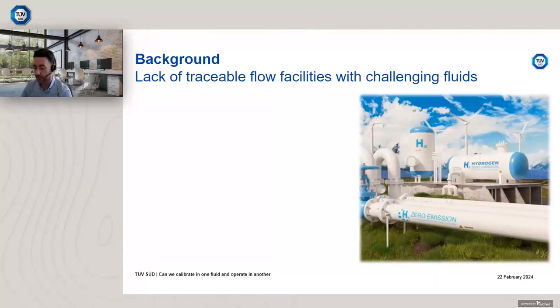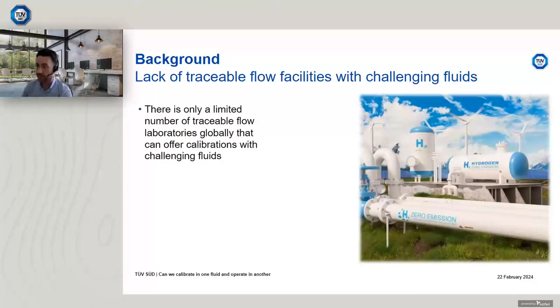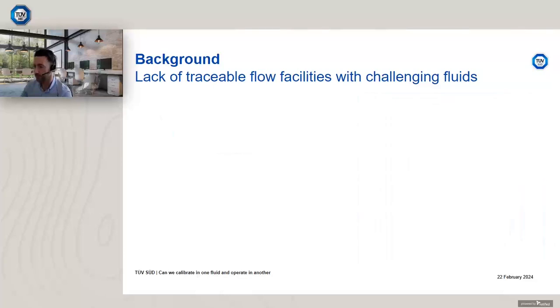Another fluid that is obviously very topical is hydrogen. And again, same as before, there's a limited number of flow facilities. There might be some that can offer gas flow, either in hydrogen flow for gas or liquid, but they're typically very, very small flow rates. There might be applications with hydrogen refueling stations, for example, very low flow, or domestic gas use trials, which we're also completing here at TÜV SÜD for gas phase hydrogen. But what about larger industrial sized flow rates? There certainly is a lack of traceable flow facilities, although there's a lot of plans in place globally, but at present there's certainly a lack of these facilities.